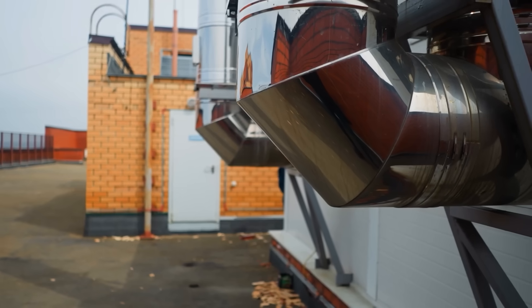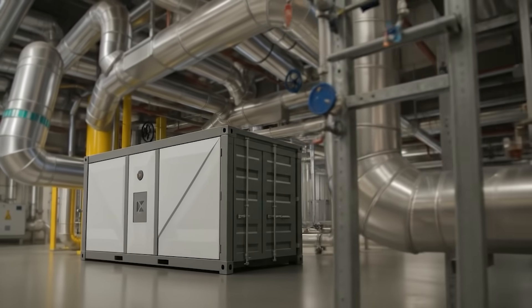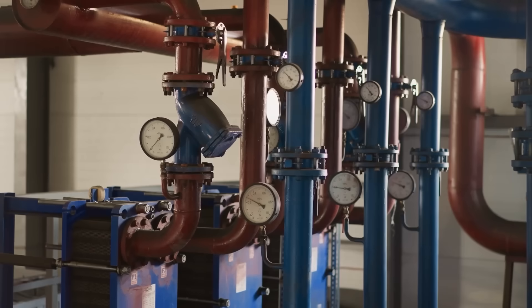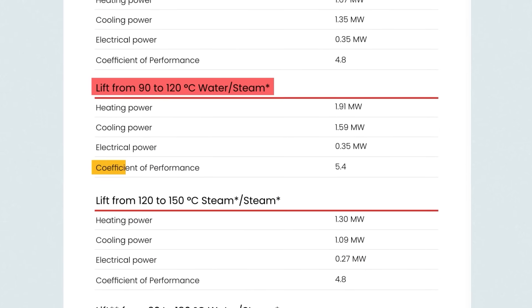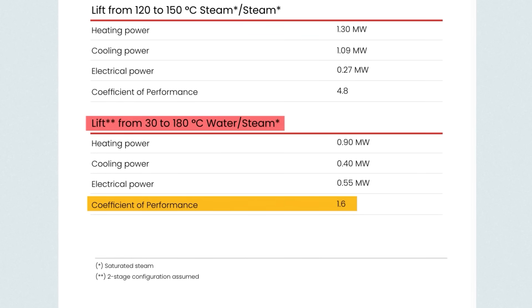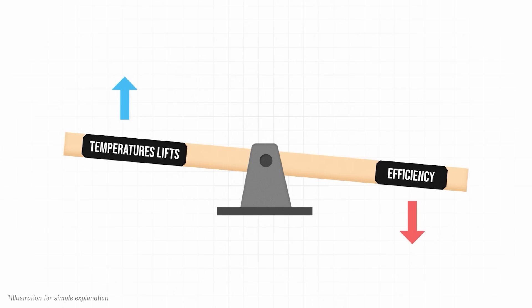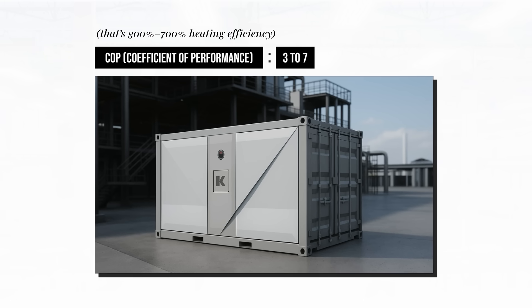All this technology has been used before, just not at these speeds, pressures, and temperatures inside heat pumps. Challenges for Carman Industries will come from ensuring the system works well across a wide range of industrial applications while still mass manufacturing it. Another challenge for both Carman and Heaton is achieving high enough coefficients of performance as they raise temperatures higher and higher. Heaton's datasheet gives a clear example: a small temperature lift allows a coefficient of performance of 4.8 — often called 480% efficiency — but at larger temperature rises similar to those required by Carman, their COP drops to just 1.6. Still impressive, but it shows the trend. Carman are advertising COP values of 3 to 7, which would be exceptionally high for such large temperature rises if they can deliver.